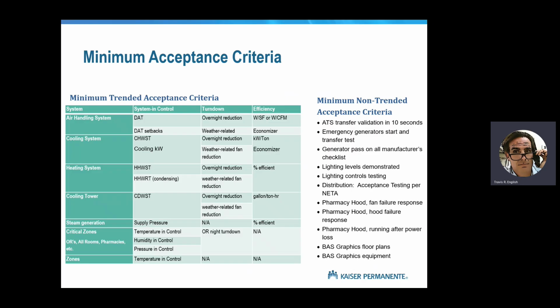more binary in nature. So as an example, if we have a boiler, first we would want to see that the system is in control. Temperatures are in control, pressures are in control, delta T is in control, flows are in control. That's what we call systems in control, right? And that is a prerequisite to anything else. Do not start working on energy efficiency if your system is not in control, right? Next, we should see turn up and turn down. So is it shutting off at night? Is it turning on during the day? Is it ramping up when it's cold out? Is it ramping down when it's hot out?